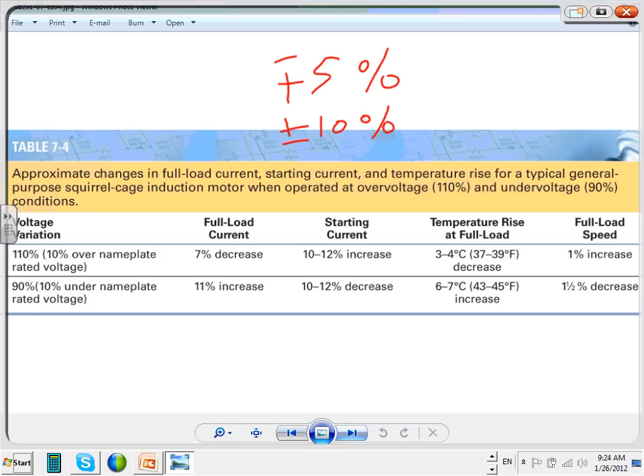If you have a voltage variation of 10% extra voltage, your overvoltage condition, the full load current decreases by 7%. That's good news. Full load went down. Starting current increases. Oops. Now my starting current increases, the temperature is going to decrease in your system, and full load speed will increase. Look what happened if you have a 10% reduction in your voltage. The current increased 11%. Now your motor is running at a higher current. The same thing, a decrease in the starting current. But look at the temperature. There's a temperature increase and a decrease in the full load speed.